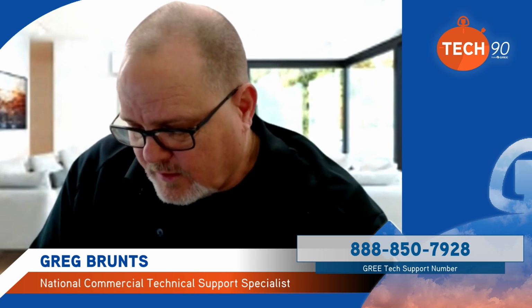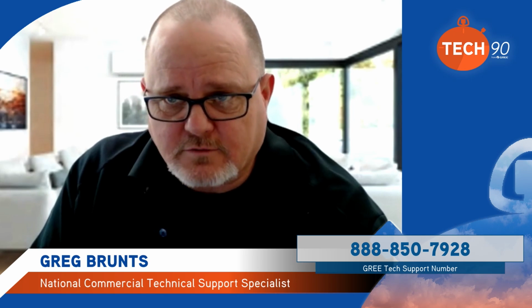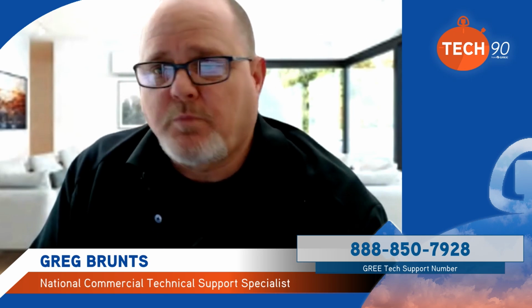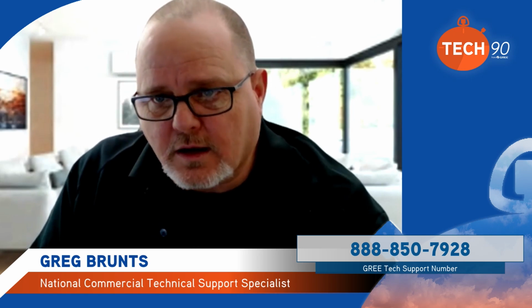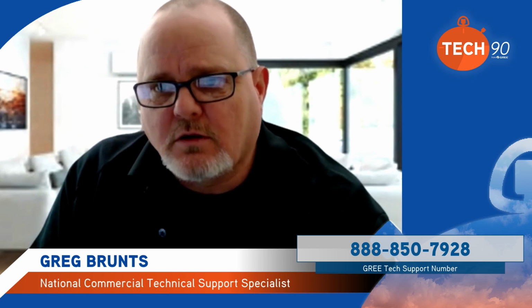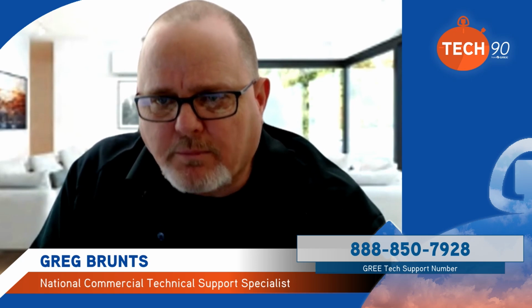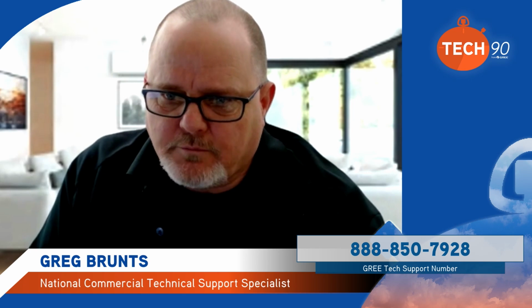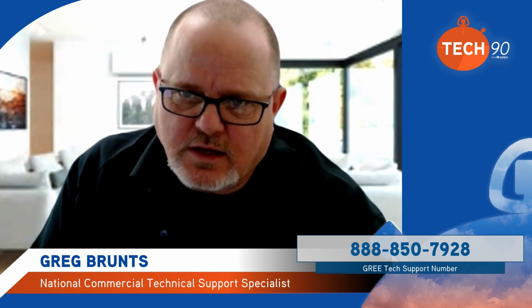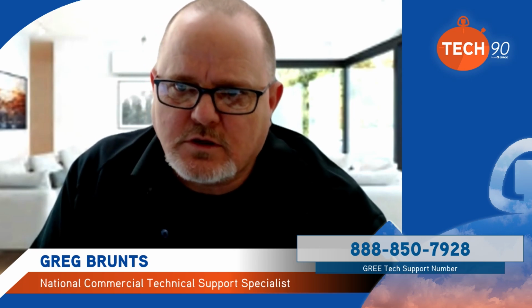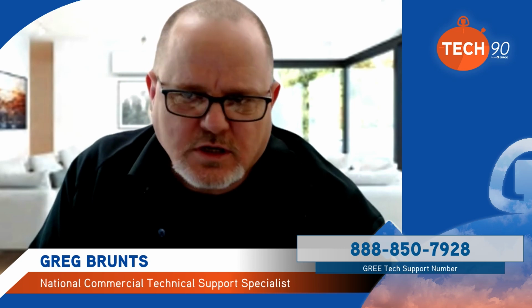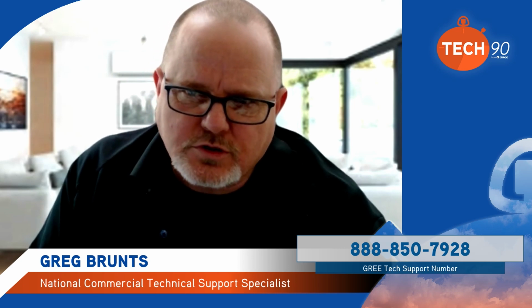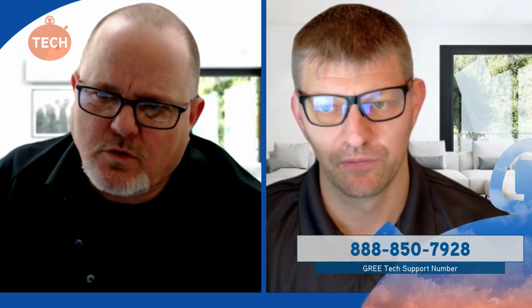Sometimes we're told things and we find out later on that it's not necessarily true. That's part of the reason why we go to the Atlanta lab and run the equipment and see it for ourselves and make sure we're giving you proper information. But I can't imagine GREE not displaying the error codes on those indoor controllers. JD, do you remember, did we produce any other error codes when they showed up on the controller? Yes, and the E6 did show up when we were messing around with the wiring, just trying to see. Which also tells me it's capable of giving me other codes.